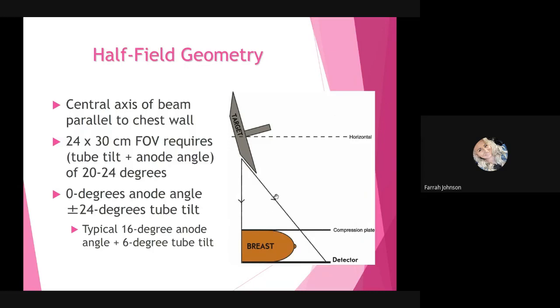And then you use the lower energy photons that are going to be on your anode side for the nipple end of the breast. Okay, same thing that we do in X-ray with utilizing the fat cat method, if you guys have ever heard of that, where you put the thicker part of a body part underneath the cathode. So for example, if you were imaging a femur, you would put the knee end of the femur underneath your anode, and you would put the thicker part underneath your cathode. Well, same thing in mammography, except now we're putting the chest wall end underneath the cathode and the nipple end of the breast underneath the anode.